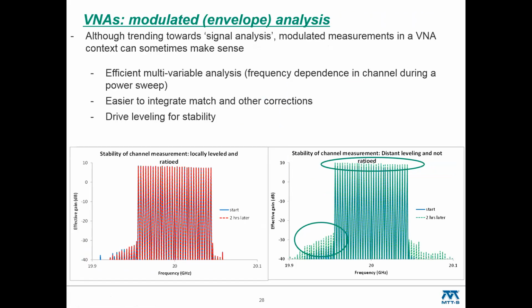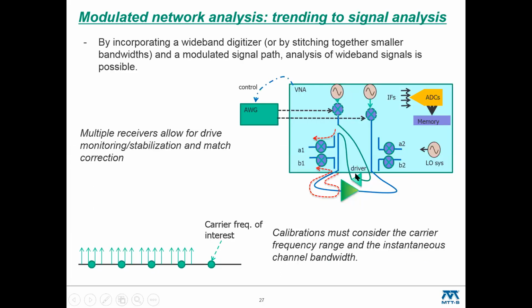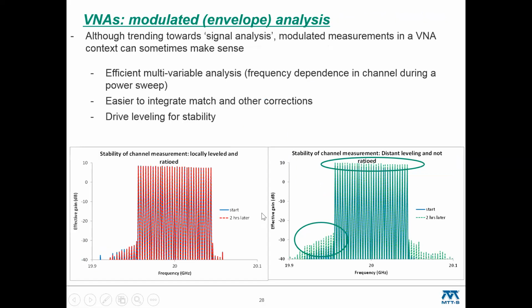So what about that ratioing and leveling kind of concept? If one was just doing signal analysis, one wouldn't think that'd be important, and it may not be all the time. But suppose in this earlier slide we had some driver preamp, and suppose that's drifting around a little bit. That could impact both the measurement and what the device is doing, and that's really what this slide is showing. If I just treat it as a native single channel kind of measurement and I came back 2 hours later, what actually happened in this case is the drive power drifted up by a couple of dB in band.